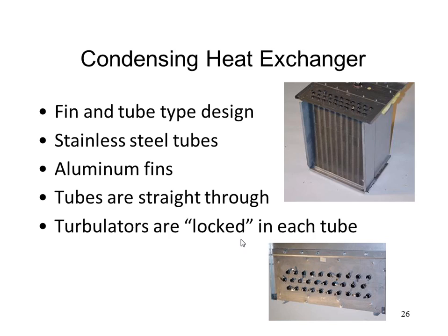The tubes are stainless steel and the fins are aluminum. And the reason we use aluminum whenever we can is aluminum is a little bit better of a heat transfer media than stainless steel is. I mean, they're both pretty good, and both of them are corrosion resistant for condensate and things like that. But the aluminum fins do a little bit better job of transferring the heat, and hence why we used them here to get a few more tenths of a percent out of this thing.